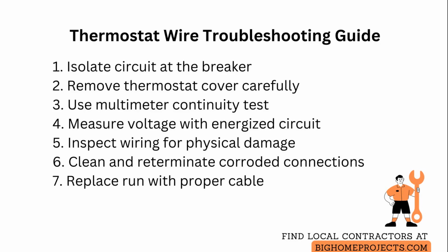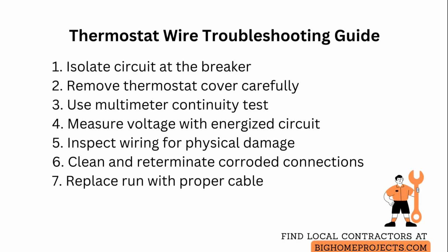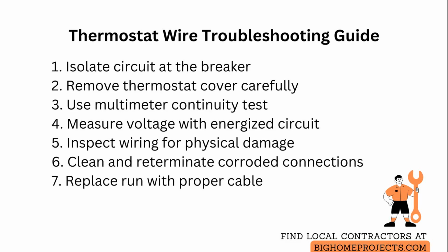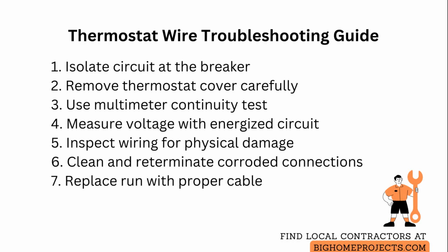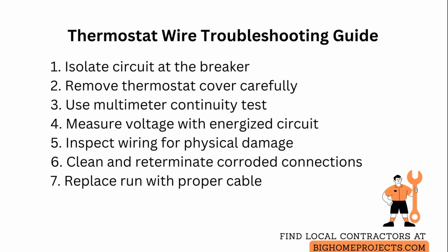Inspect wire insulation along accessible runs in basements, attics, and behind access panels for nicks, rodent chew marks, brittle insulation, or paint-covered splices that can hide breaks. Note that cloth-covered or woven sheath wiring common in very old houses degrades and may expose conductors. Check terminal screws and wire ferrules for corrosion or loose clamping that creates high resistance.